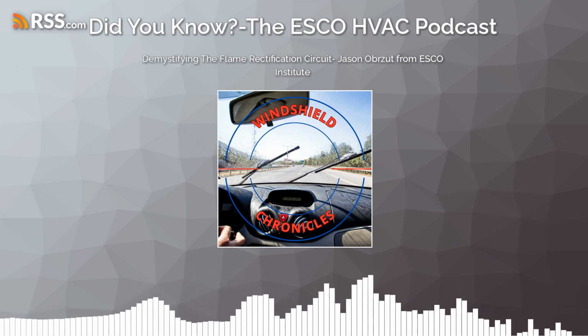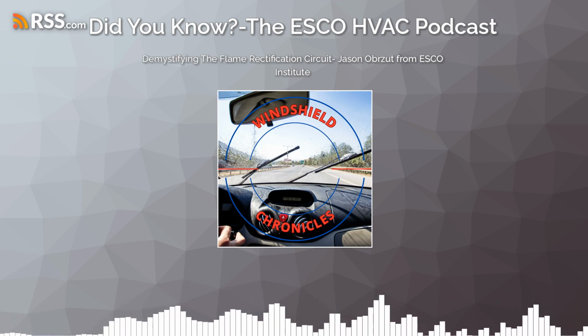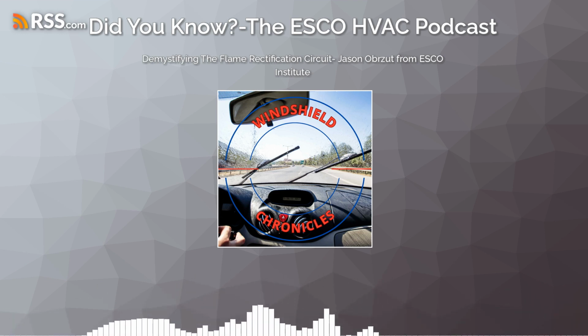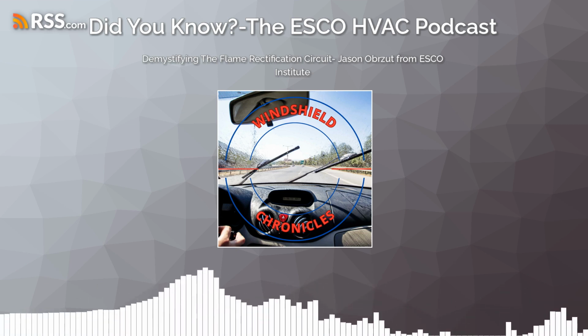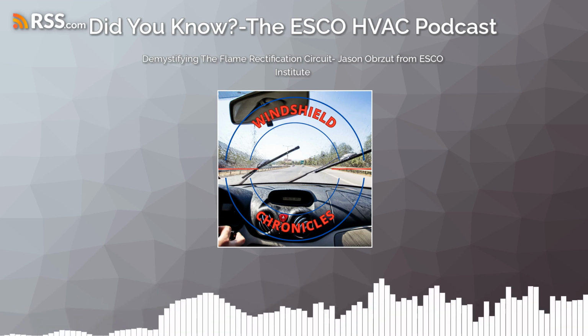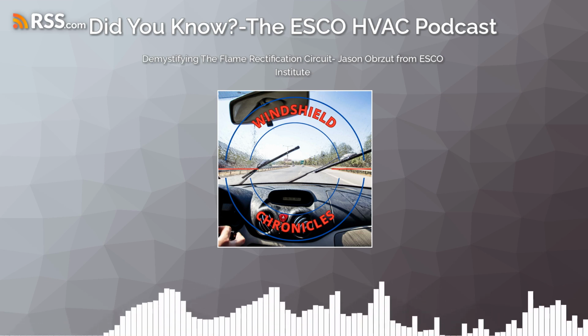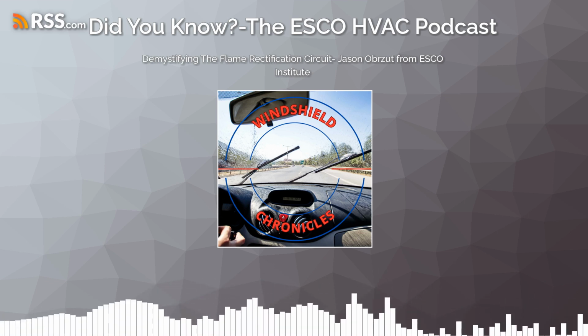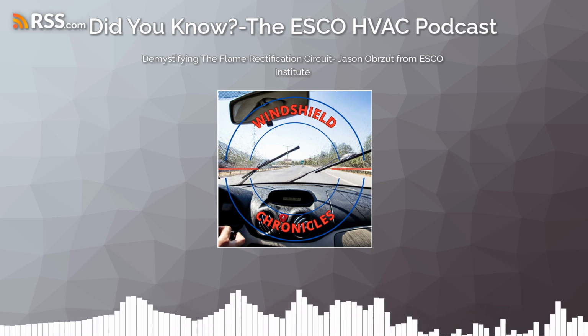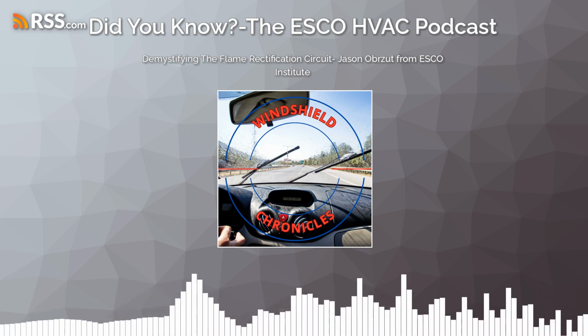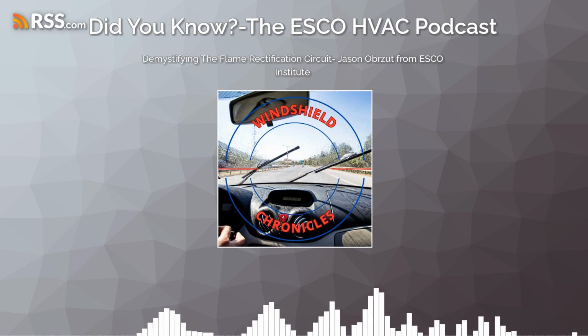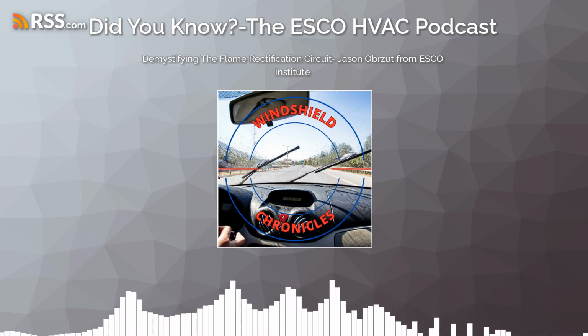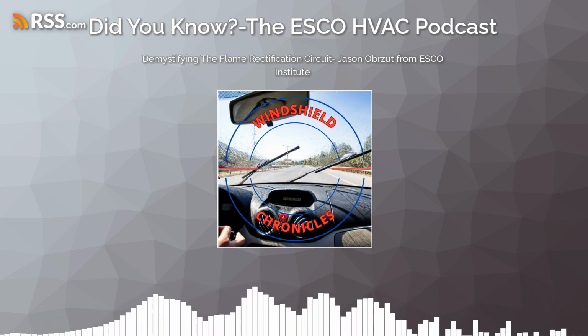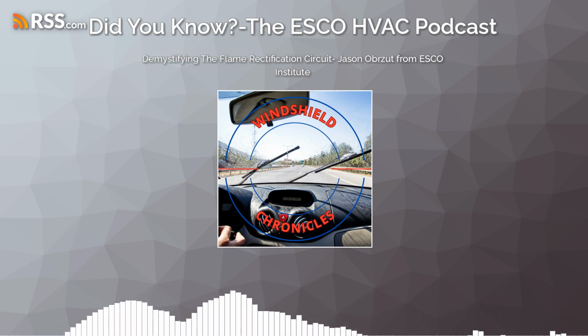I want to point something out real quick, Cliff. Yes. When your meter is in that position, it allows voltage to pass through it. Right. So if you accidentally touch ground with either end of that, you're going to have some fireworks. So you have the insulated clips on your alligator clips there. Don't let the meter lead touch the burner or the furnace. Sure. It's got to be firmly connected to the wire and to the flame sensor, and nowhere can we introduce the ground or we're going to have some problems.